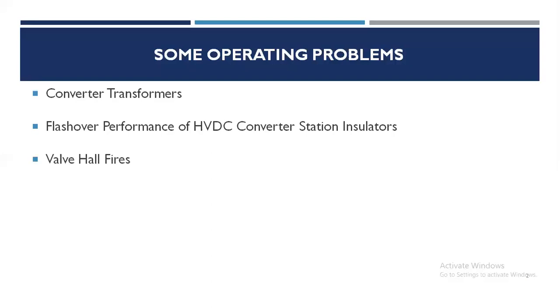Third problem is regarding valve hall fires. In 1989, a converter in Itaipu HVDC station in Brazil was totally destroyed due to a fire, probably caused by a leakage in the cooling system associated with corrosion. Subsequently, there were fires in valve halls in Rihand in India, Sylmar in USA, and Gezhouba in China. In the Sylmar converter station of Pacific DC Intertie, the valves were completely destroyed in 1993. The adjacent valve hall had extensive smoke damage requiring much arduous cleaning.